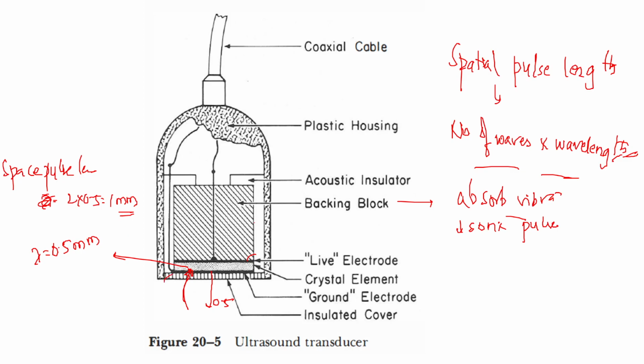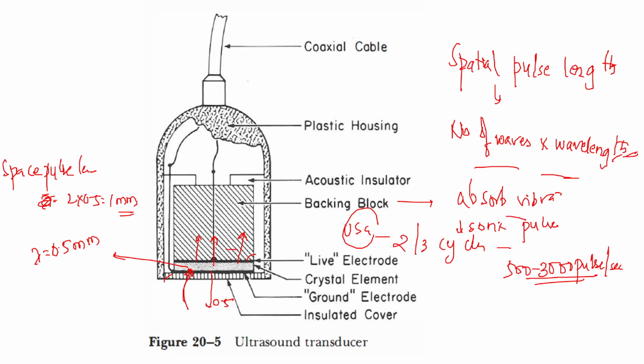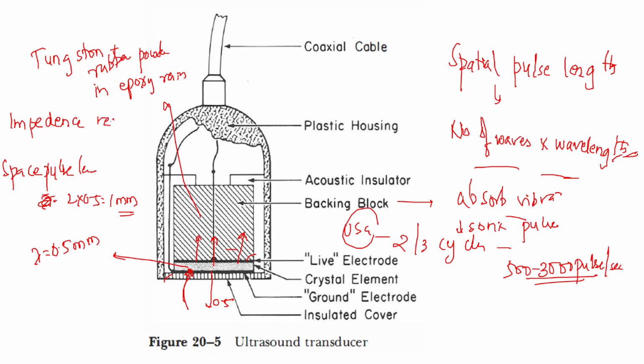Generally, in the normal ultrasound imaging transducers which we use in any department, 2 to 3 cycles will occur, with between 500 to 3000 pulses per second. There will be 500 to 3000 pulses of ultrasound beams received by this transducer. All of them should be received by the backing block. The backing block will absorb all of this energy, so it should be able to absorb all of the sound energy. The backing block is mainly made up of tungsten with rubber powder in epoxy resin. The ratio of tungsten to resin will mainly satisfy the impedance requirements.